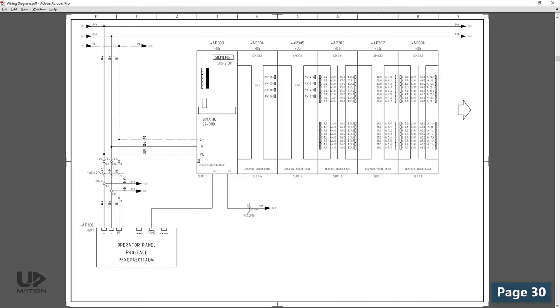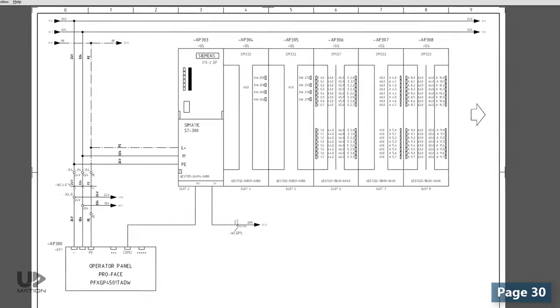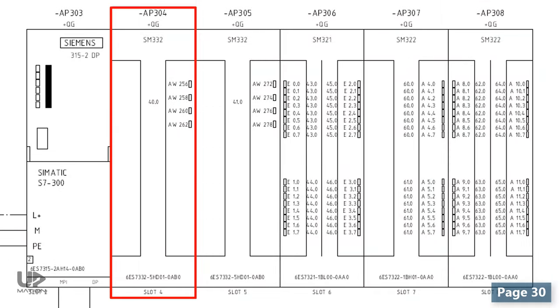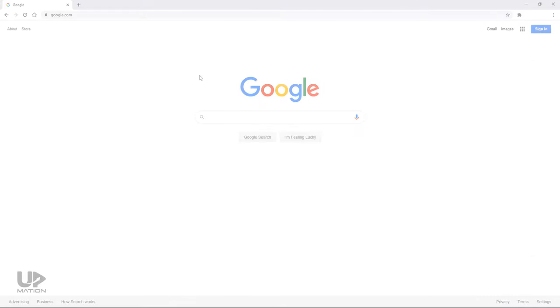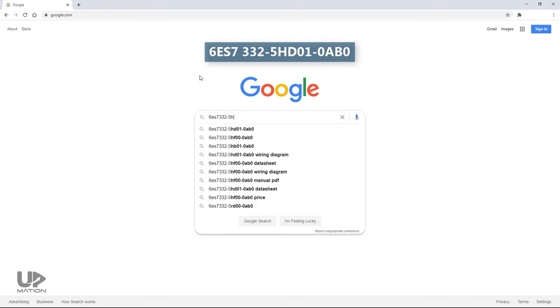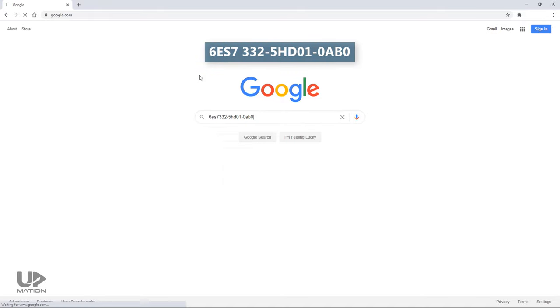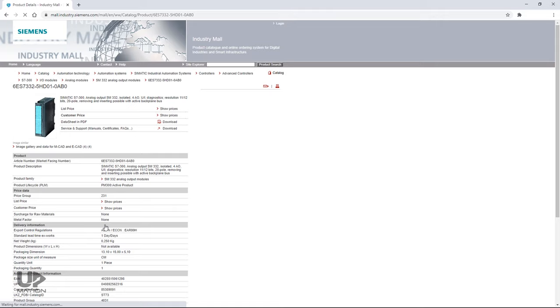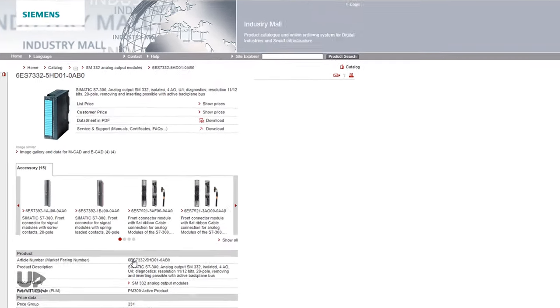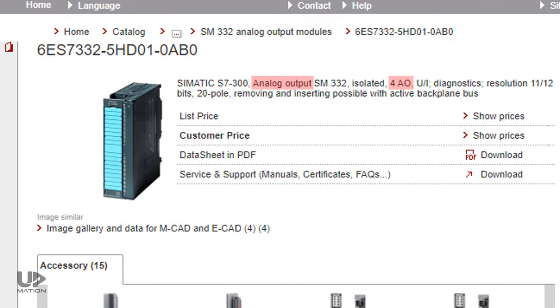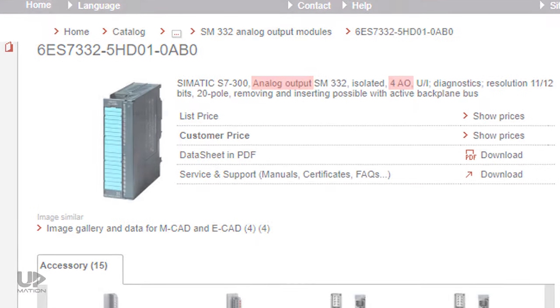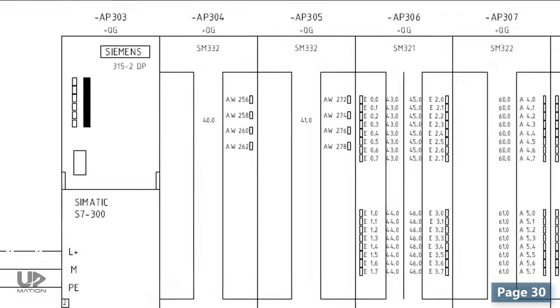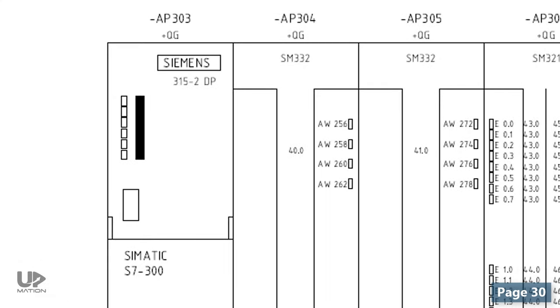Let's get back to page 30 to continue with our first PLC card. If you've been familiar with the Siemens PLC cards and modules, or you simply google this order number, you'll understand that this is an analog output card with 4 channels. And each channel is dedicated to a single device. The page number where we can find the wiring diagram for this card is here in the middle, Page 40.